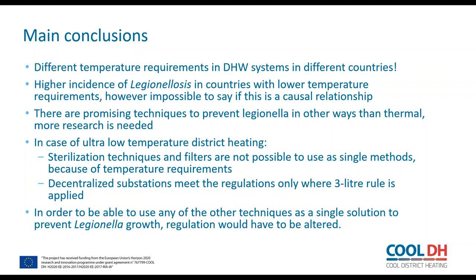There are promising techniques that can prevent legionella in other ways than thermal treatment. However, more research is needed to say if it will be safe to use them as a single method. In the case of low temperature district heating with a supply temperature below 50 degrees, techniques such as sterilization filters are not possible to use as a single method today due to the temperature requirements. However, the decentralized substation could be used, but only in the countries where the 3-liter rule is applied.